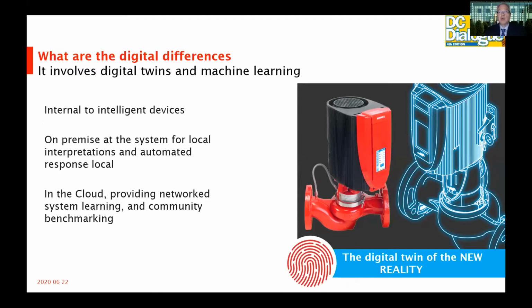In this case, I've shown a small pump, and it has a digital twin embedded inside of it. It knows from the factory what its performance print was, its equipment performance map, and it's able to observe changes over time. So we can adjust its behavior to compensate for external changes in the environment or internal changes within the device itself. So that digital twin isn't a static twin, it's an evolving twin. So over time, as the conditions change, we see how that equipment performance map for that digital twin has changed, and it opens the door for some machine learning applications to optimize at the device level and the system level.